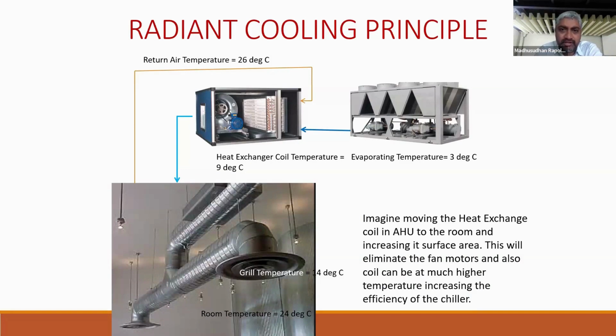In the conventional HVAC air conditioning system, what we do is, if we have to cool a room at 24 degrees centigrade, return air at maybe 24, 26 degrees centigrade is passed over a heat exchanger, a coil in which chilled water is flowing at an average of 9 degrees centigrade. Now, this air and this coil is the only place where the heat exchange happens. The entire heat exchange of whatever space is being cooled happens here, and therefore this is a very dense heat exchange. It needs to happen in less than a second, and therefore the coil temperature needs to be very cold.